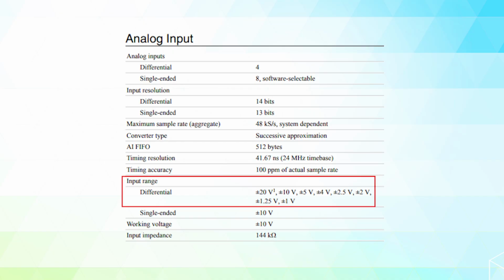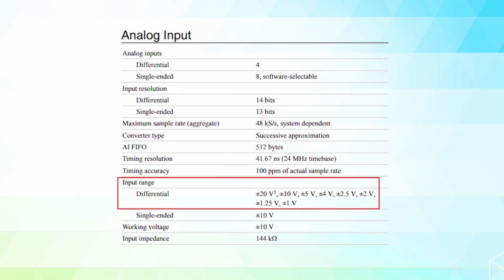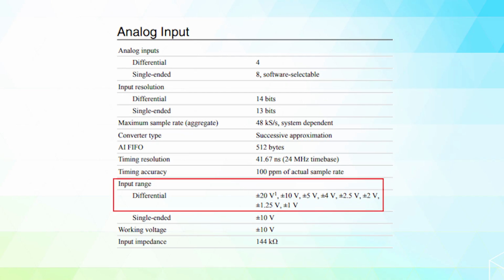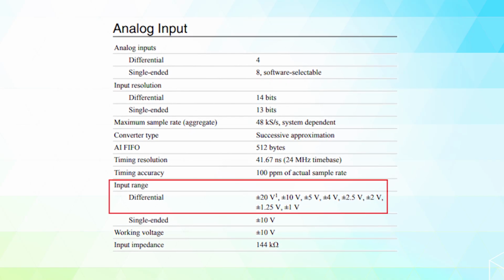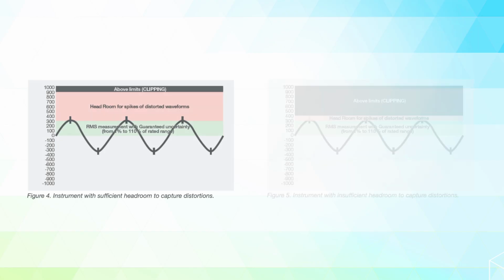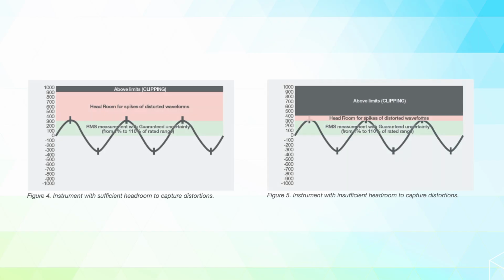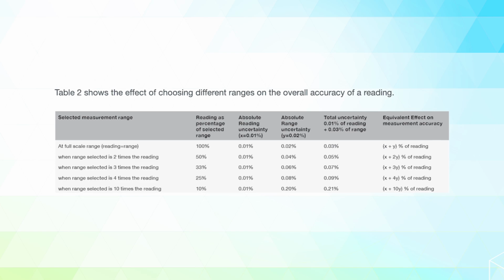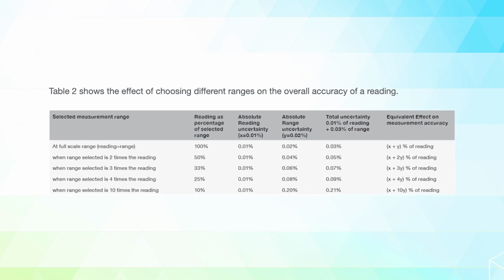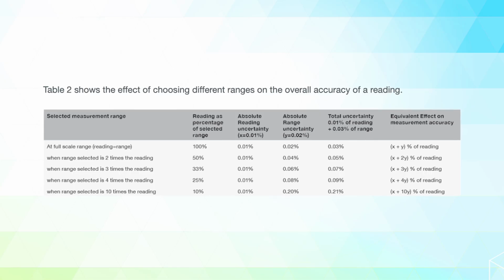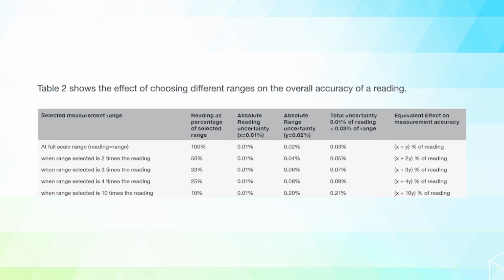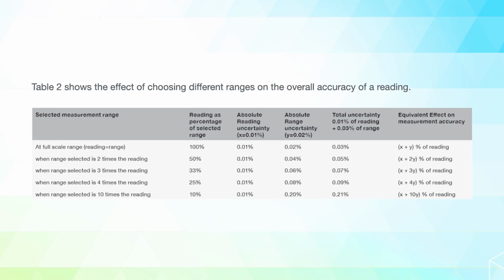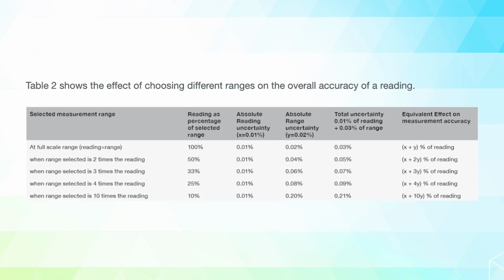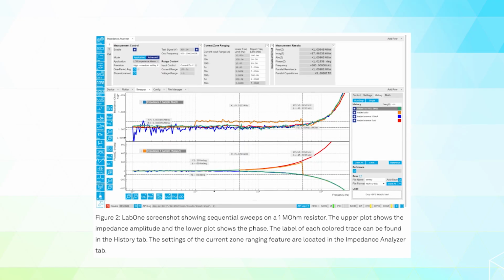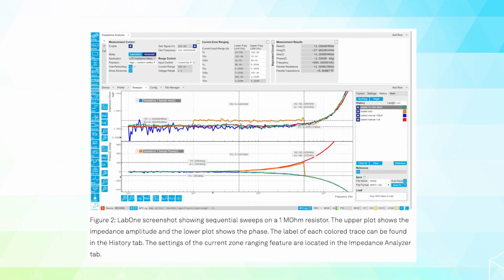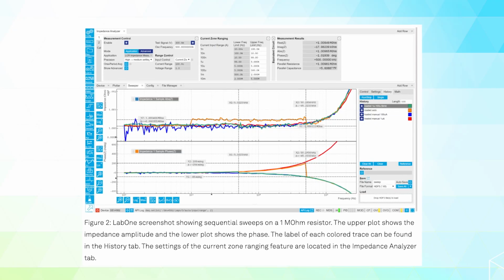Input range also plays a major role in real-world accuracy. Many DAQ devices and instruments allow you to select ranges such as positive negative 10 volts, positive negative 5 volts, positive negative 1 volt, or even smaller ranges depending on the device. Choosing the right range helps the instrument use its available resolution more effectively. For example, if you are measuring a 100 millivolt signal on a positive negative 10 volt range, you are spreading the device's resolution across a much wider range than necessary. You may still get a measurement, but you are not taking full advantage of the hardware. When you choose the smallest range that safely contains your signal, you improve measurement detail and often improve practical accuracy.